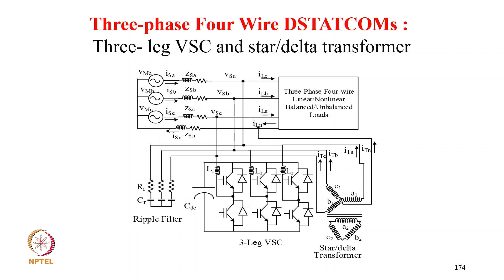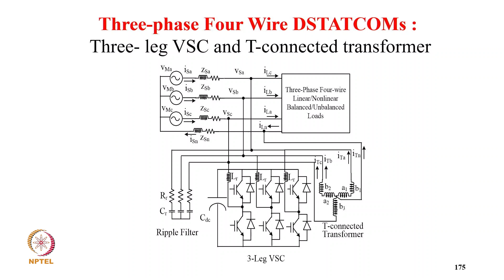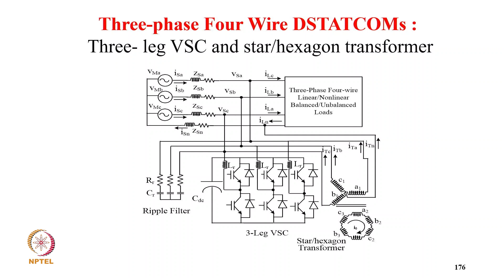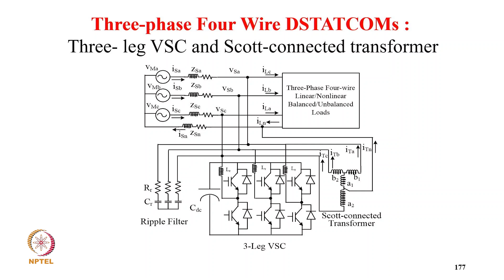So it really makes the neutral current compensation zero. Then 3-phase 3-leg VSC with T-connected transformer. The transformer neutral is able to compensate for the neutral current of the supply by supplying the load neutral current locally. Then the 3-phase 3-leg with the star hexagon. Here also we provide a star, but you need the closed path. So the hexagon of the secondary provides the closed path for the circulating harmonic, so that your neutral point is stable. Then the Scott-connected transformer for neutral current compensation, 3-leg voltage source converter used for the compensation.